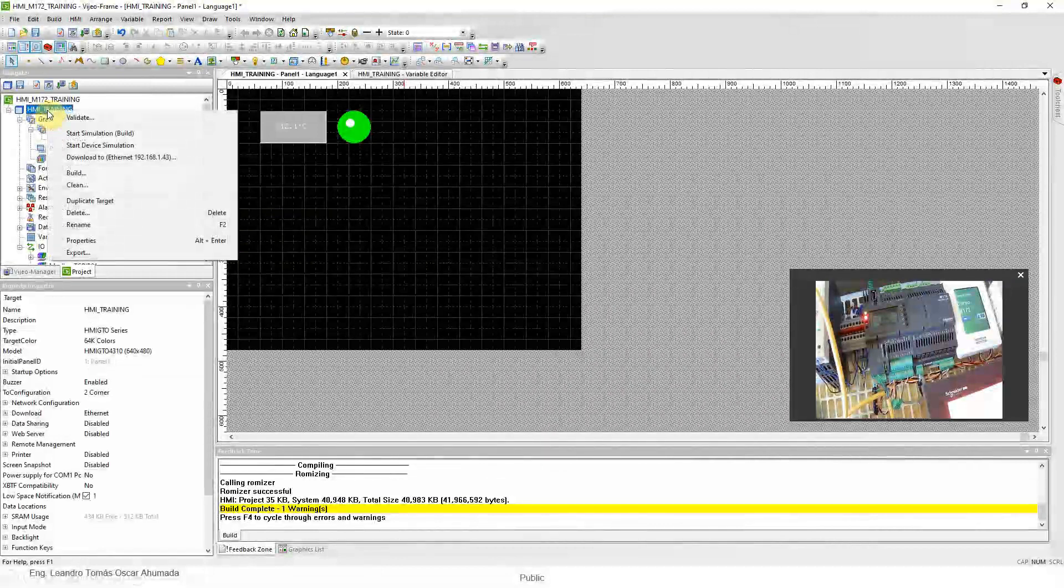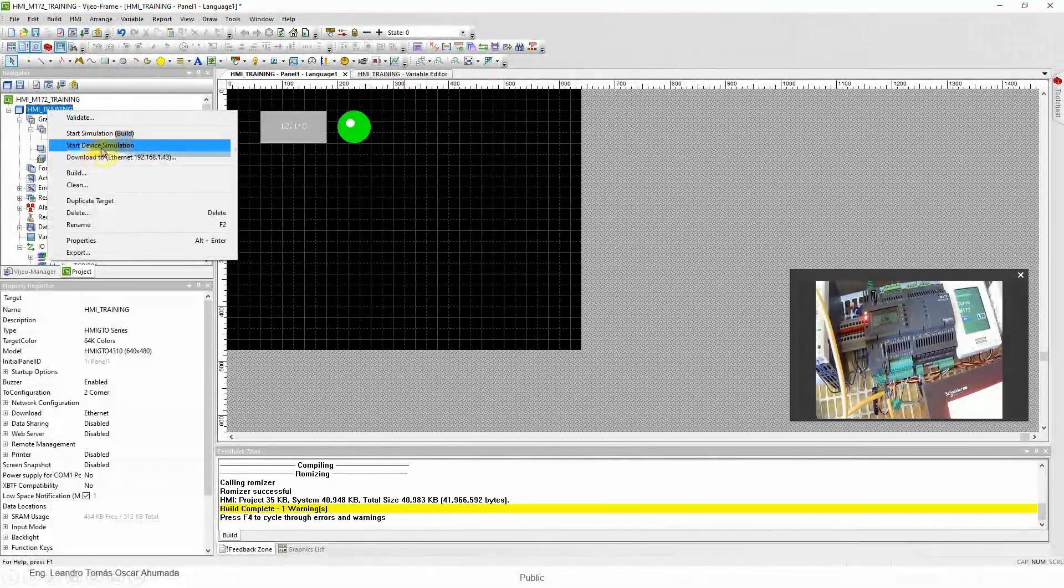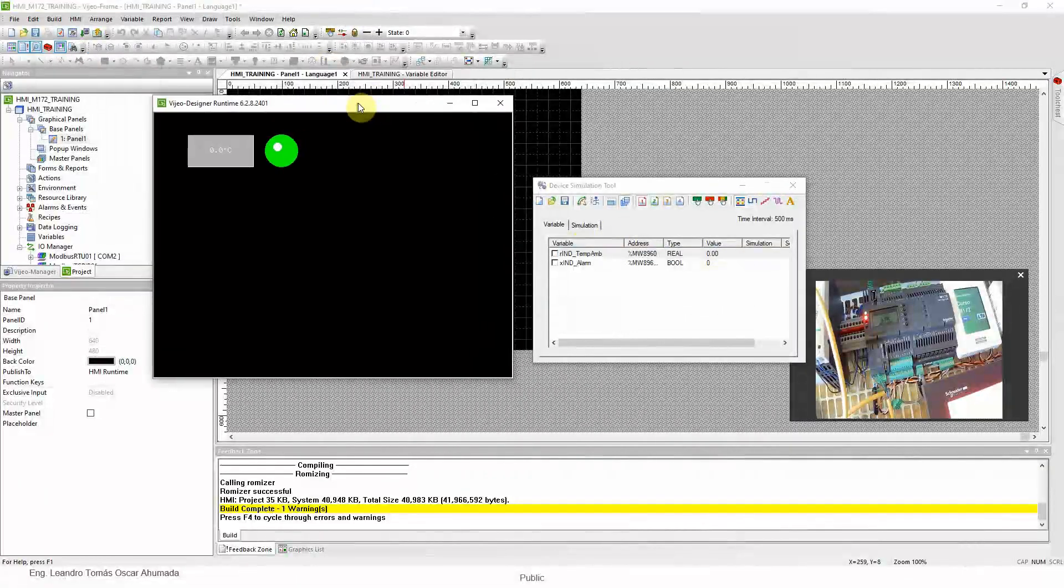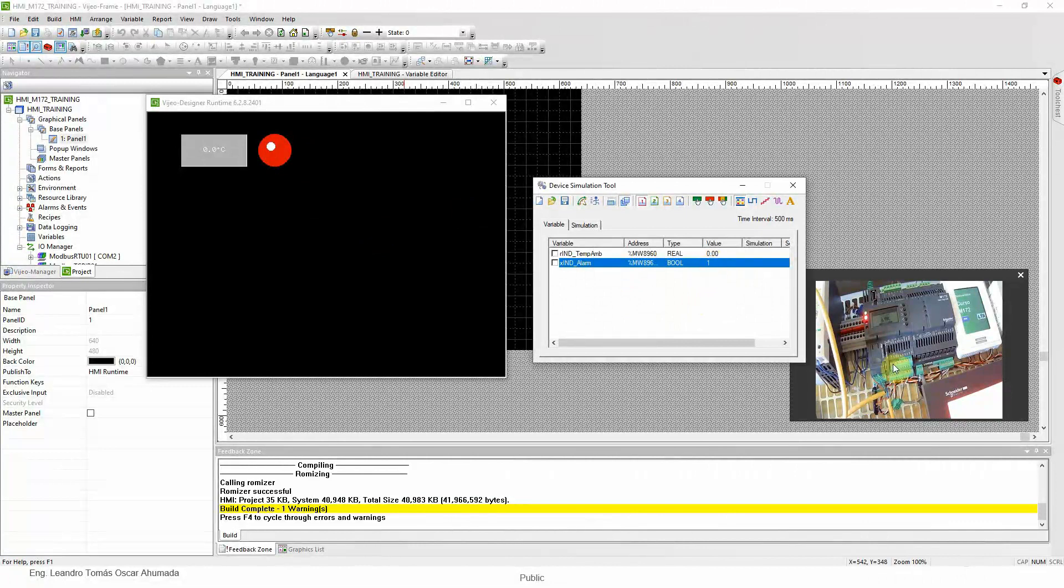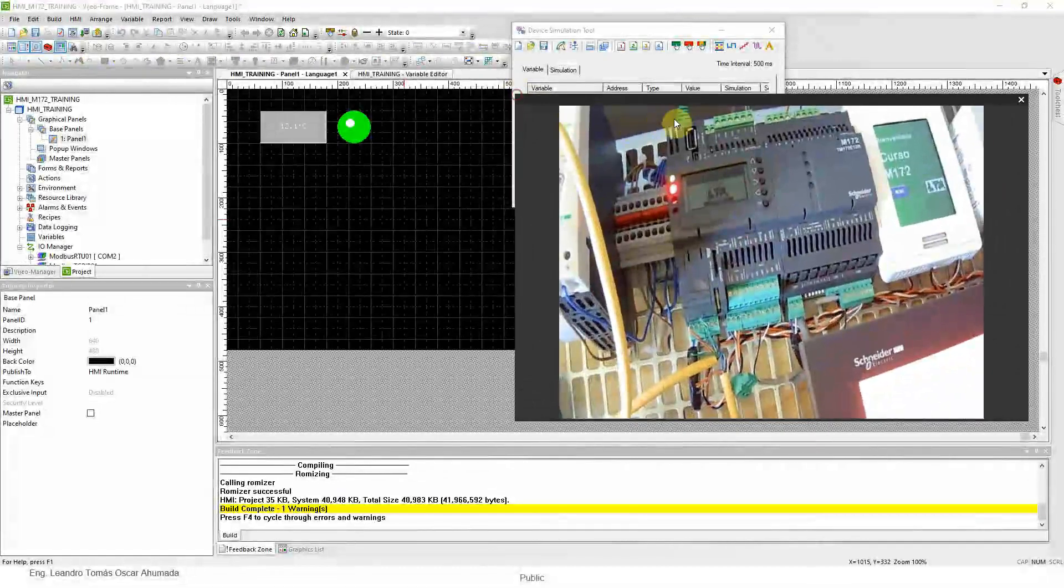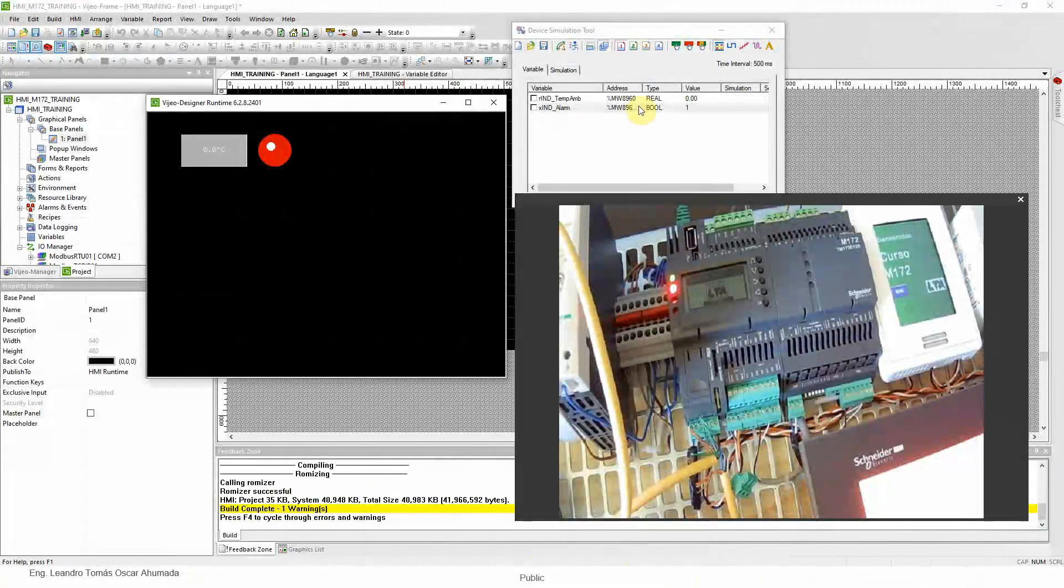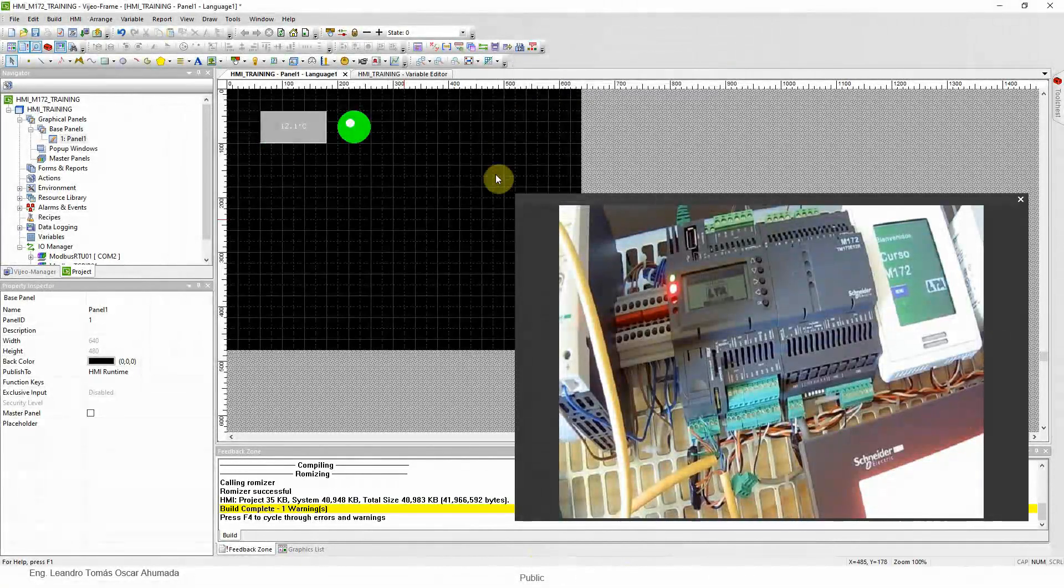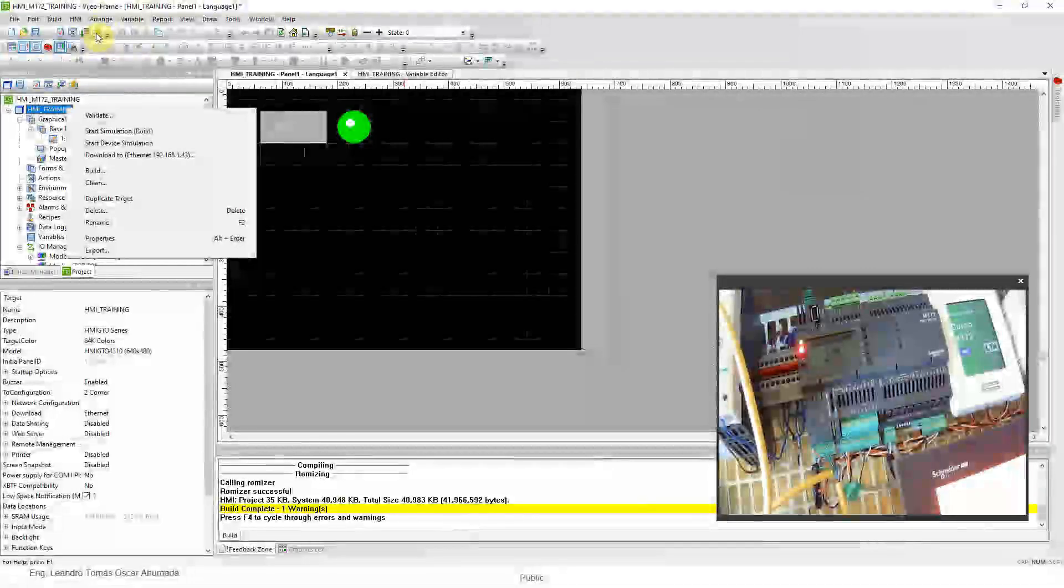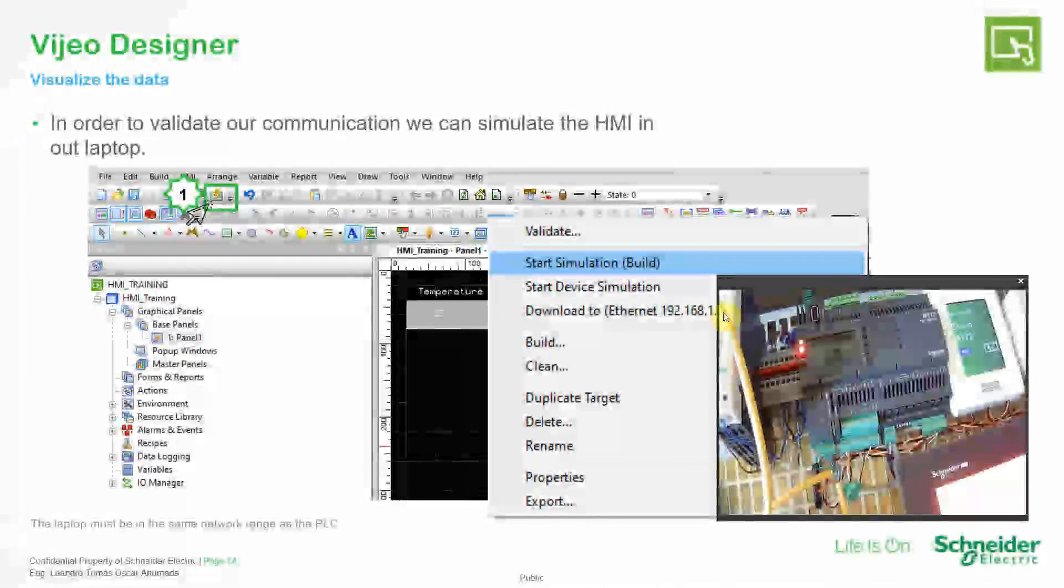Another way is to use the HMI in this part. It would be the target. Right-click on it and you have the start simulation. If you use this start device simulation, it will simulate the devices that you have connection with. For example, this. See, that is not the real PLC. The real PLC is not disconnected. Let me just maximize this. See, the real PLC is not disconnected. So if we want to simulate, probably the best solution for you would be to just start simulation instead of device simulation, and you can use also this icon to simulate the HMI in your laptop.